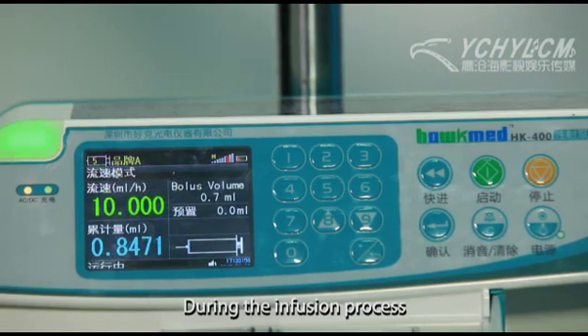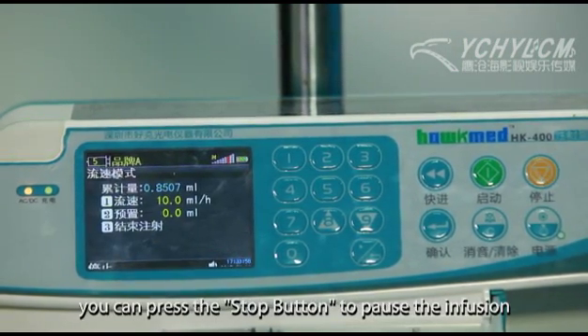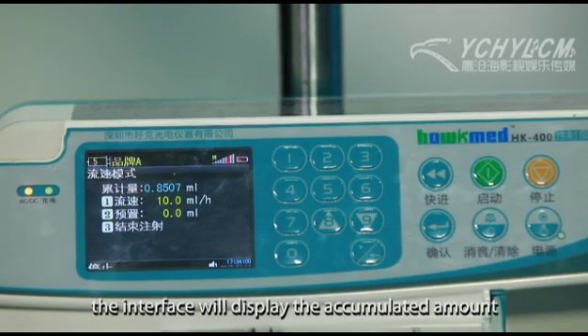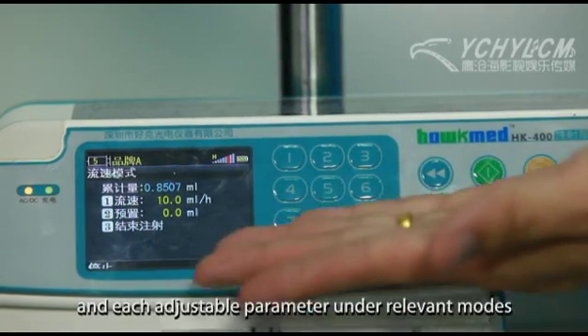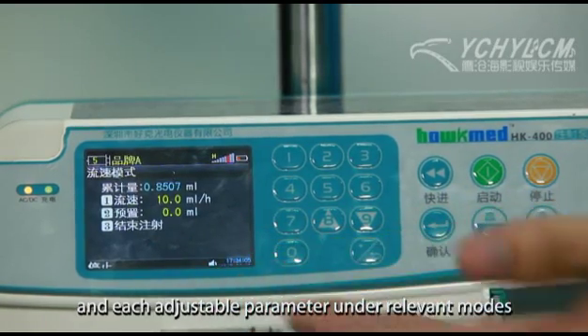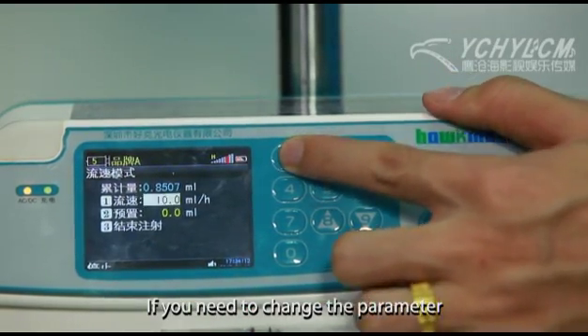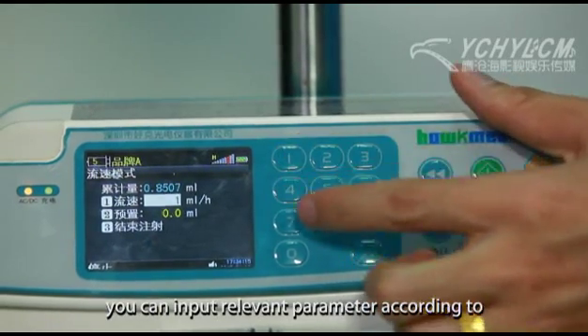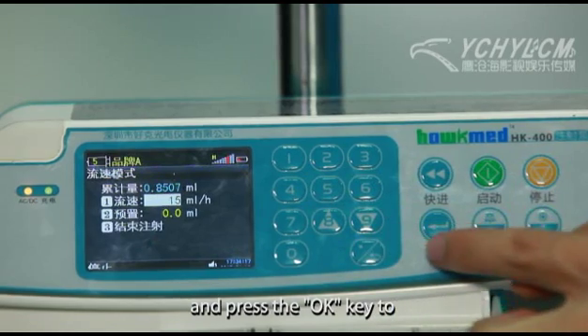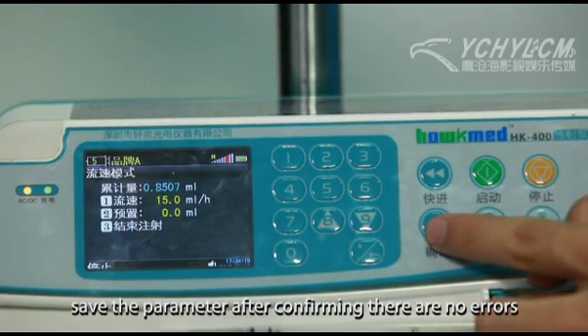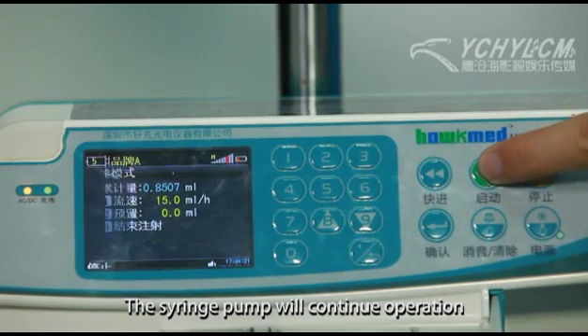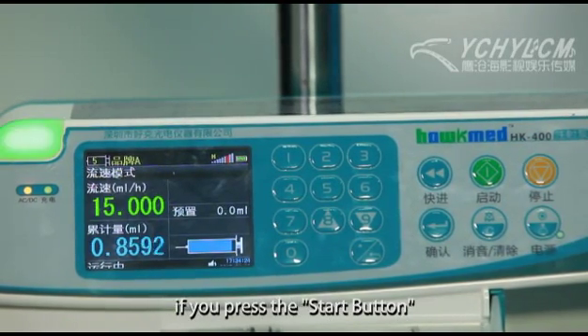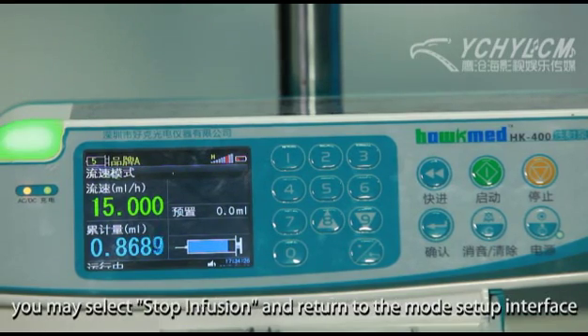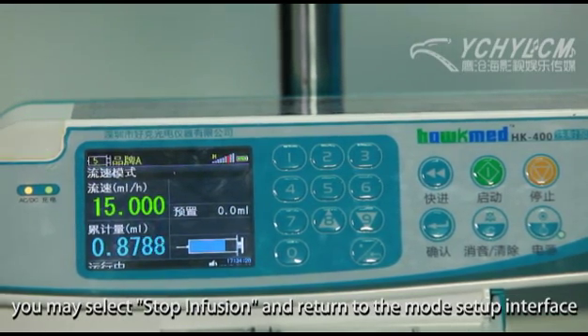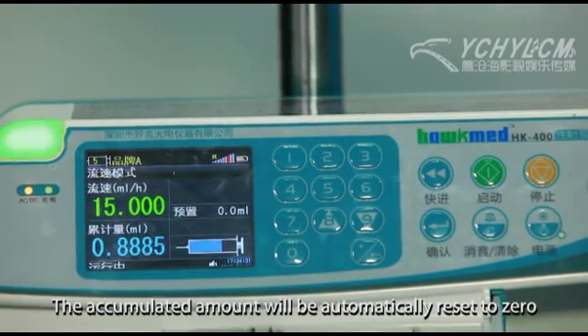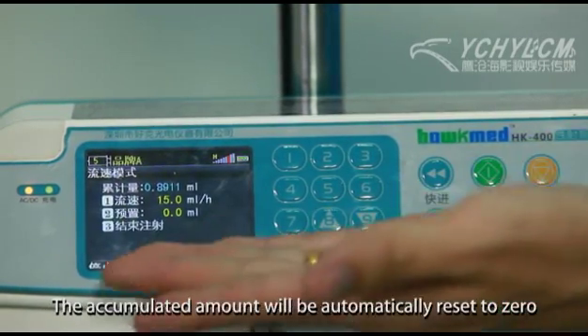During the infusion process, you can press the Stop button to pause the infusion. At this time, the interface will display the accumulated amount and each adjustable parameter under relevant modes. If you need to change the parameter, you can input relevant parameter according to your needs and press the OK key to save the parameter after confirming there are no errors. The syringe pump will continue operation if you press the Start button. If you hope to stop the infusion, you may select Stop Infusion and return to the Mode Setup interface. The accumulated amount will be automatically reset to 0.